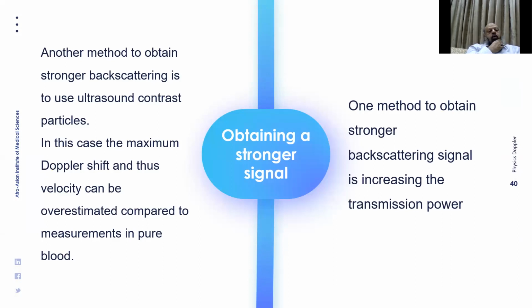Another method to obtain stronger back scattering is to use ultrasound contrast particles. In this case, the maximum Doppler shift, and thus velocity, can be overestimated compared to measurements in pure blood. One method to obtain a stronger back scattering signal is increasing the transmission power.